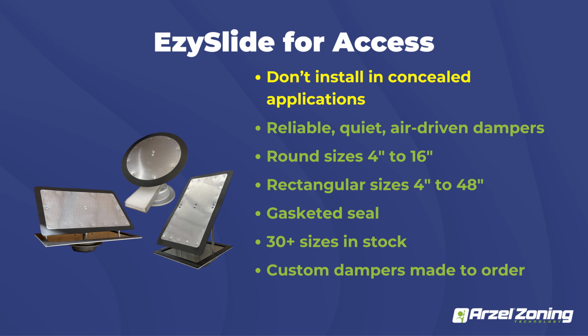So if you have a 6-inch duct, you could do a 5-inch damper, so you can alleviate some of that extra static into another area of the home, maybe an entryway or a mud room, something that can handle a little bit more over conditioning to allow that static pressure relief. Besides, of course, using a bypass or something like that.